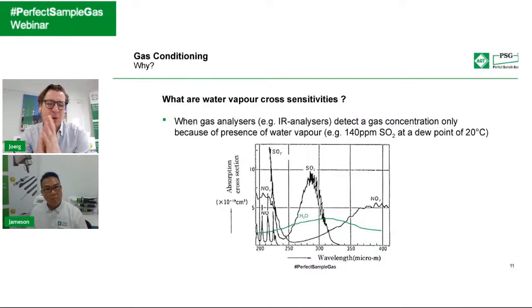This is the reason why it's so important that we have a constant and low outlet dew point, because in this case the analyzer can calibrate the amount of remaining water in order to be very accurate when measuring the SO2.